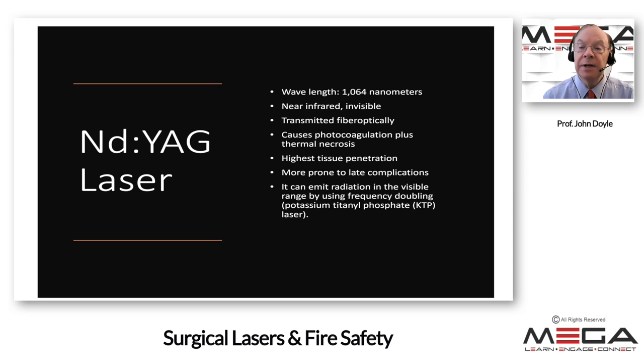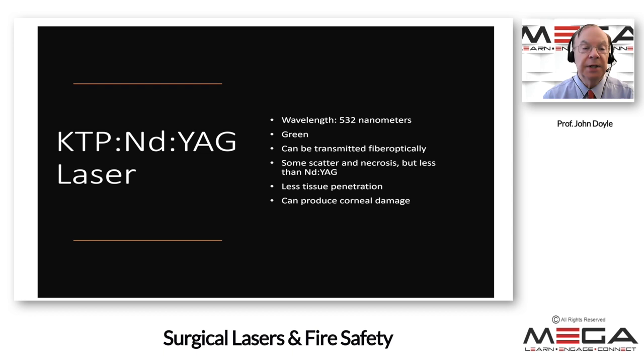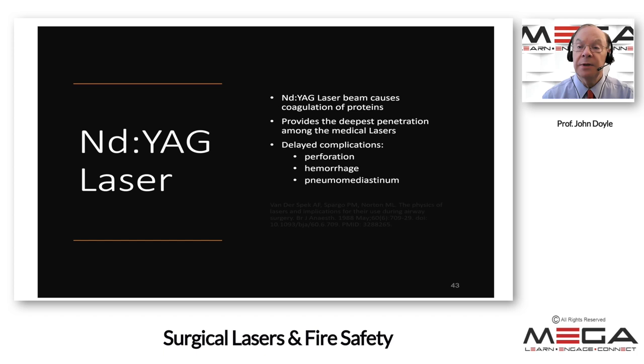The neodymium YAG laser has a wavelength just over 1,000 nanometers — it is infrared but can be transmitted fiberoptically. It causes photocoagulation plus thermal necrosis, and its key feature is a high level of tissue penetration, making it more prone to late complications. It can emit radiation in the visible range by using frequency doubling via the KTP laser, which brings the wavelength down to 532 nanometers and makes it green. The KTP can also be transmitted fiberoptically, produces some scatter and necrosis but less than the Nd:YAG, and has less tissue penetration.